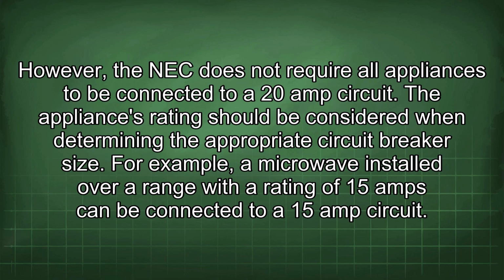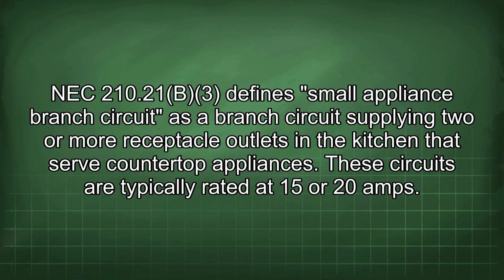For example, a microwave installed over a range with a rating of 15 amps can be connected to a 15 amp circuit. NEC 210.21b3 defines small appliance branch circuit as a branch circuit supplying 2 or more receptacle outlets in the kitchen that serve countertop appliances. These circuits are typically rated at 15 or 20 amps.